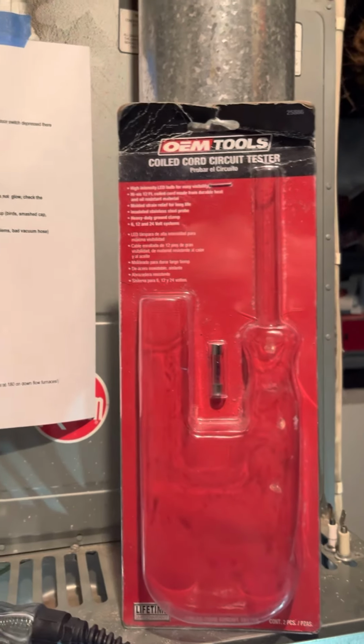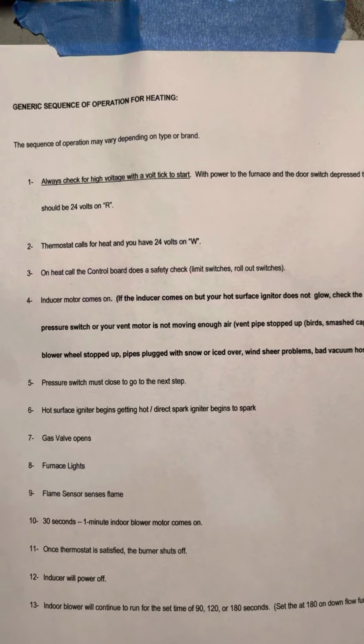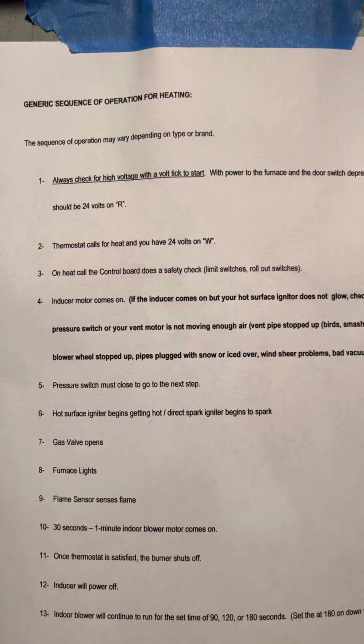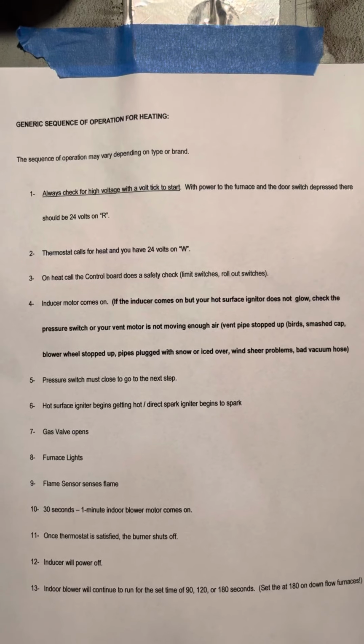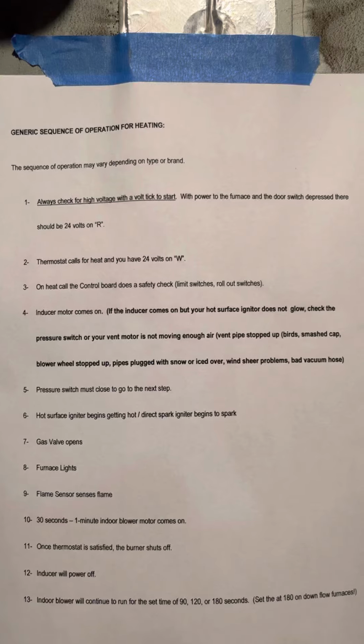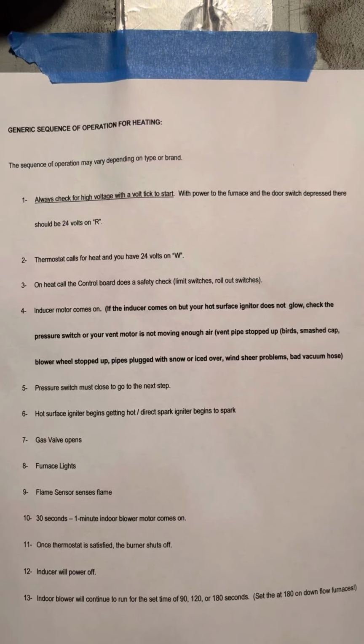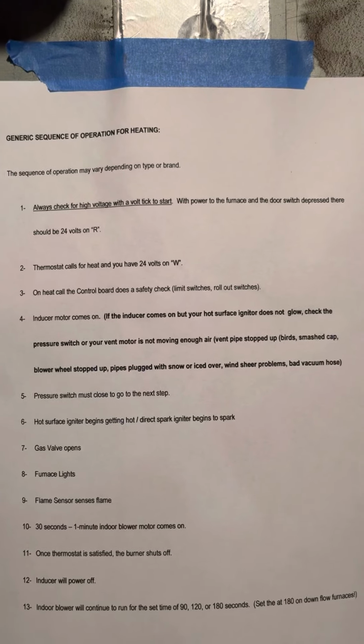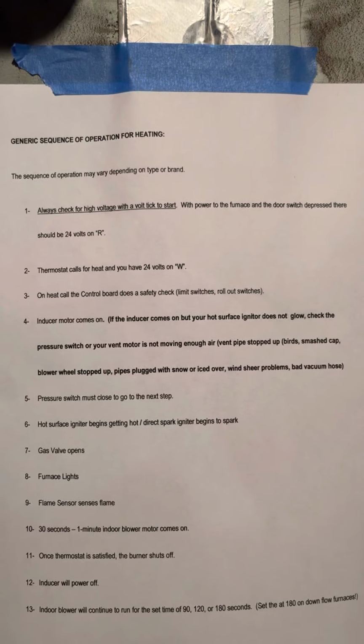The first thing that you need to know is what the sequence of operation is. Every piece of equipment has a sequence of operation. This one's a generic one. So what we're going to have on a sequence of operation for a regular furnace is 120 volts of power coming into the furnace and into the integrated furnace control. That 120 volts is going to have to be the right polarity, and it should have an equipment ground, and that's needed so that the flame sense will work.